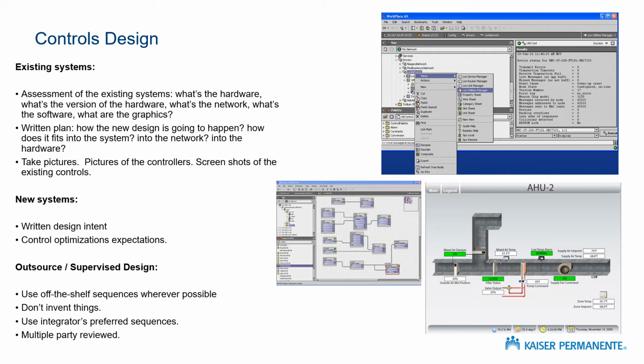Now let's talk practically though, because as I said, most of us in the design engineering field are not actually the engineer of the control system, and we are, compared to the guys who program control systems, vastly inexperienced in this. So in order to procure controls, we're going to need a set of controls details, control specifications, and written sequences, right? So the best thing to do, the smart thing to do, is to outsource and supervise that design using a set of parameters, right? Use off-the-shelf sequences wherever possible and cite their sources. So we tell you to use ASHRAE Guideline 36. Title 24 actually has some intended sequences of operation. So does ASHRAE 90.1.